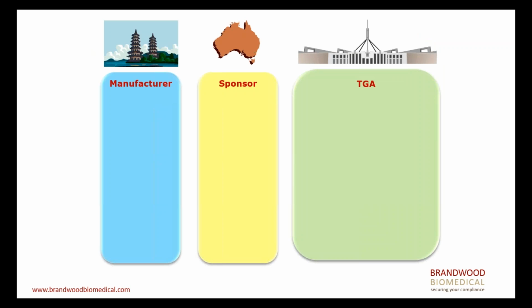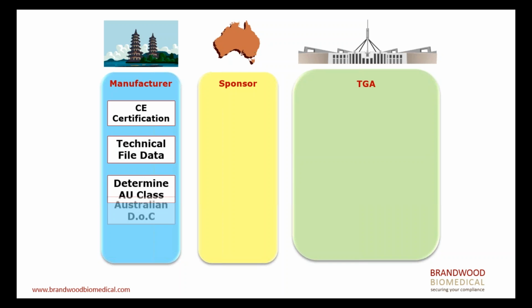So this is really still high level, but it's intended to be step-by-step as to how you can register. You've really got three key parties involved. The first one is the legal manufacturer, and the legal manufacturer will have all the documentation, the CE certification, technical file data. They would need to determine the classification in Australia, and they'd also need to have an Australian declaration of conformity. This is assuming that a device can go through CE certification. Now, you also must have an Australian sponsor, and this must be a legal entity locally based in Australia, and they will be legally responsible for holding licenses.